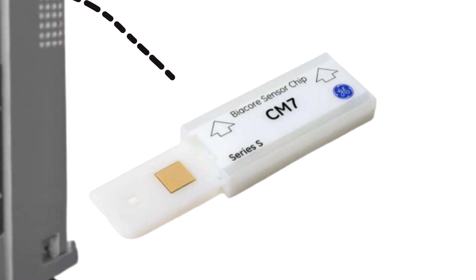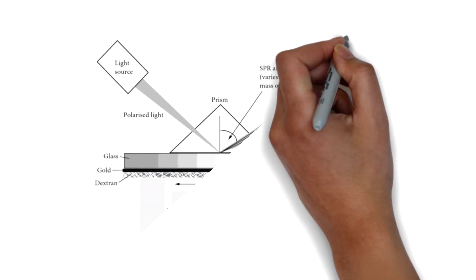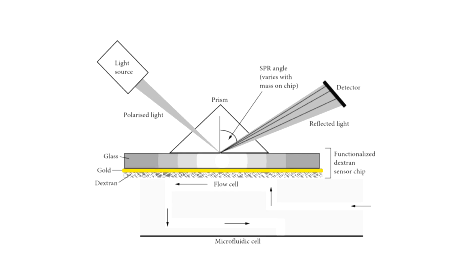Let's talk about the sensor chip now. This is where all the magic happens. In this chip, there is a glass slide coated with a thin layer of gold film. On top of this film is commonly a carboxylated dextran matrix to which the ligand is attached and immobilized.